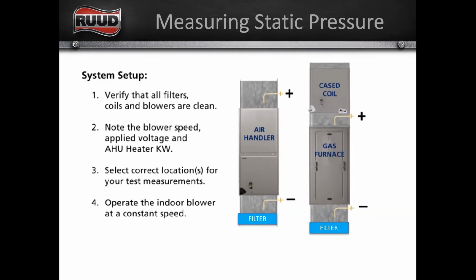And then another question was on the probe placement. A couple of questions on the probe placement. So the question was, the probe needs to be in the air, are you saying that the probe to measure static, make sure it's flat against the wall so the air pushes against it instead of flowing in the air? And no, what he's saying is, if you look at that probe, you want to make sure that the holes in the pitot tube aren't in the actual flow of the airstream, or you'll be reading velocity pressure instead of static pressure. So the probes are typically designed at a 90-degree angle. So when you point that 90 degrees in the airstream, the holes are actually on the side of that tube and not getting the airflow directly into the holes of that pitot tube.